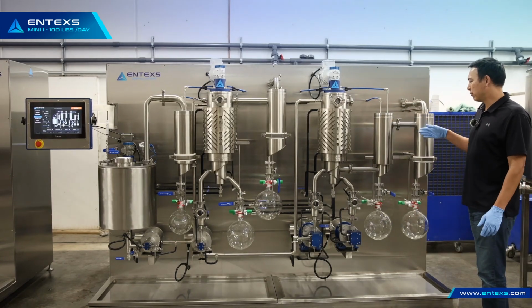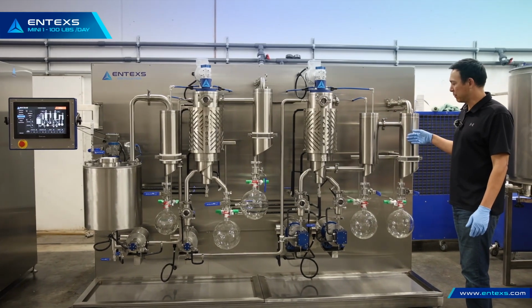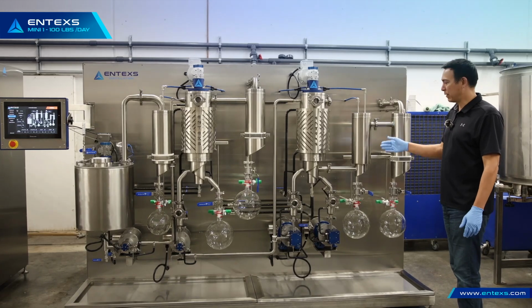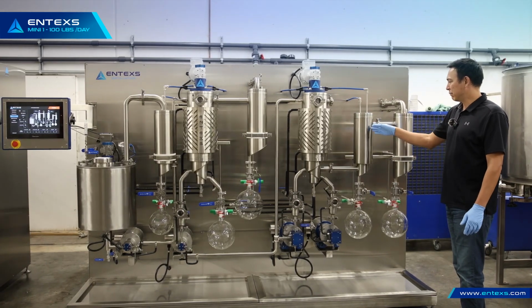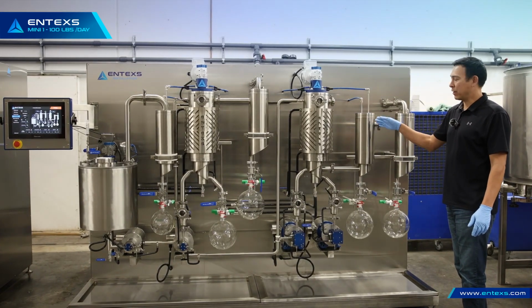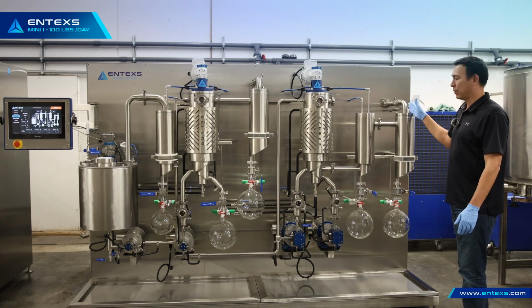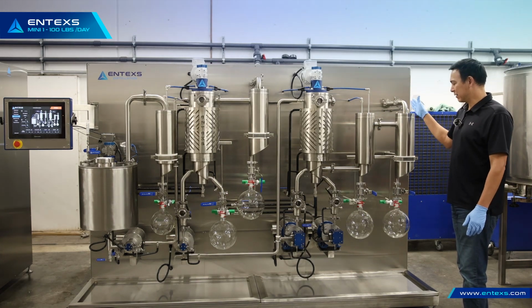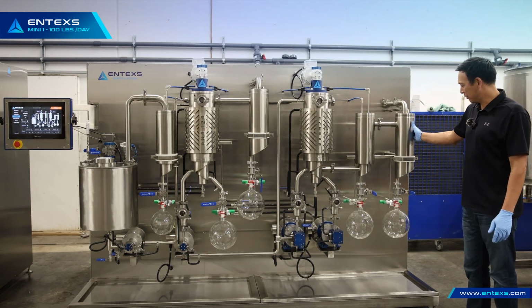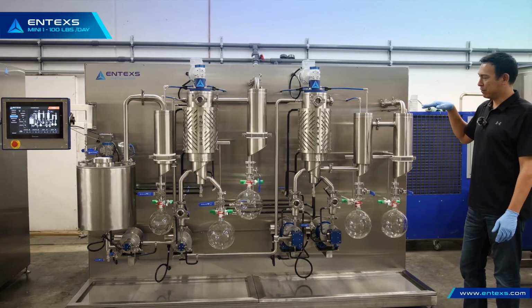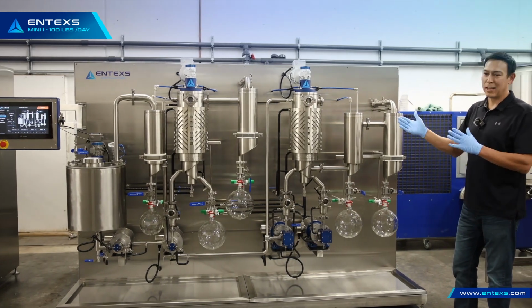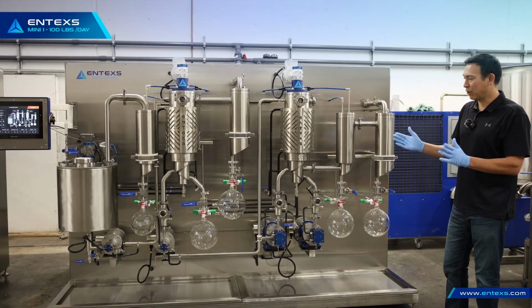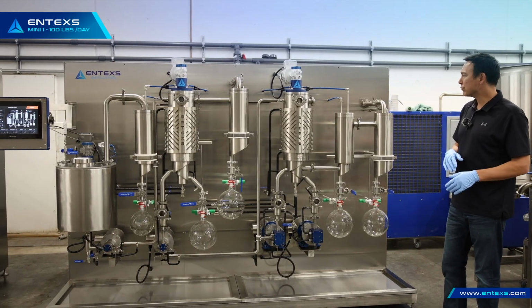This has a dual cold trap system to protect the vacuum system pumps and also maintain vacuum level, one running off of the ULT chiller and one off of the liquid nitrogen system. This is a very cold trap that can reach levels down in the 10 millitorr range even, which is very low vacuum for this type of system.